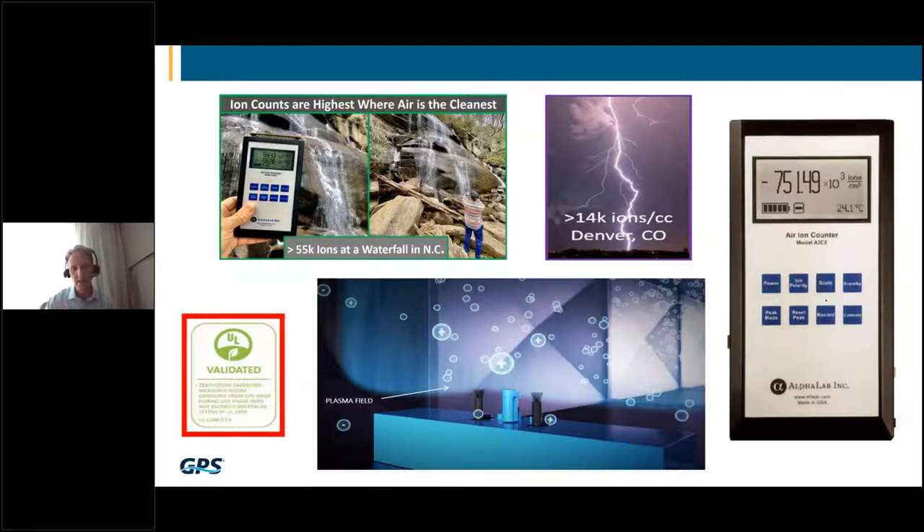There are also no replacement parts whatsoever on this product. Once you install it and wire it up — rated for 24, 110, 208, or 230 volts — your life cycle cost is basically your first installed cost. Energy consumption is typically less than 15 watts; the device shown here is four to six watts. Very little energy consumption, no maintenance, no replacement parts. That's another key differentiator with regards to needlepoint bipolar ionization versus almost any other air cleaning product.